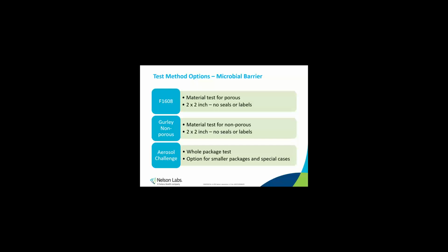Gurley non-porous verification uses a Gurley porosity tester to confirm that there's no significant passage of air over a 1 hour time block. Per ISO 11607, a demonstration that the material is non-porous will satisfy the microbial requirement. This is based on the idea that if air can't get through, then neither can microbes. And the Gurley is a pass-fail test.